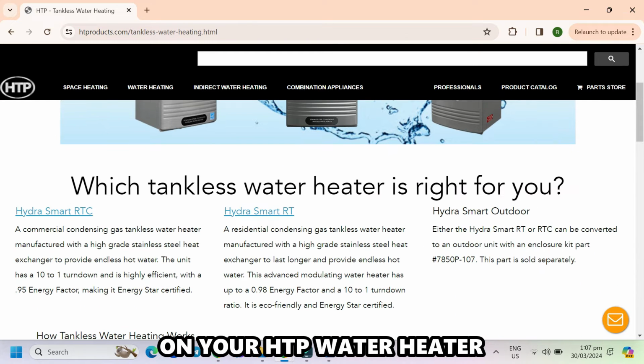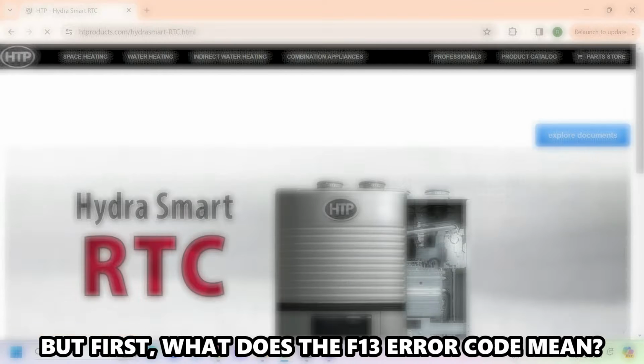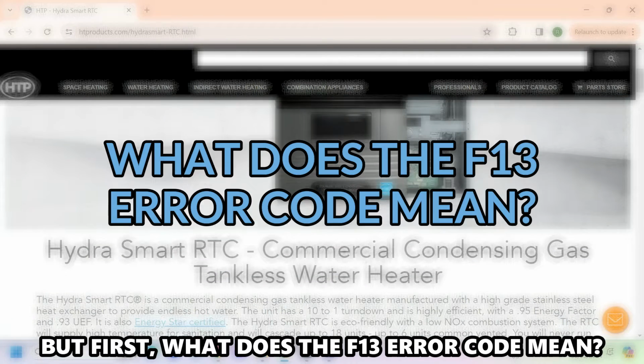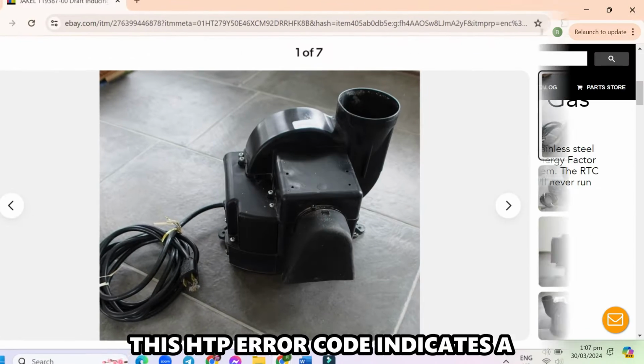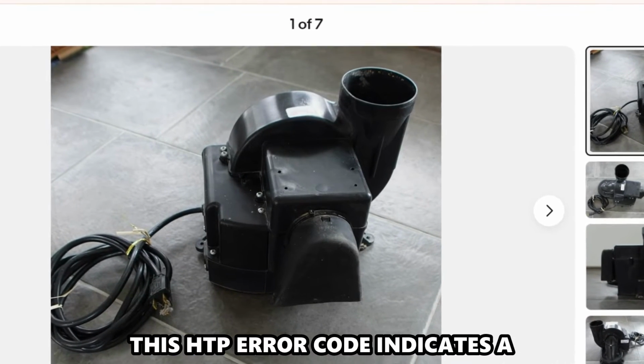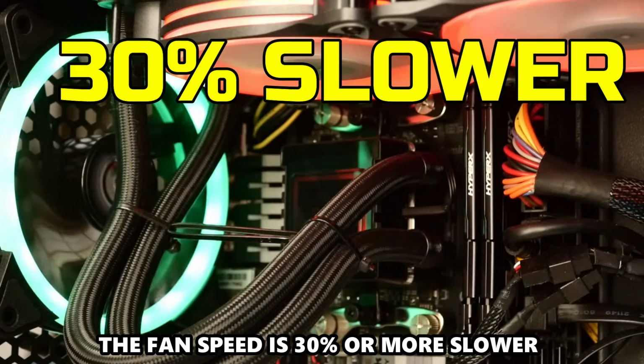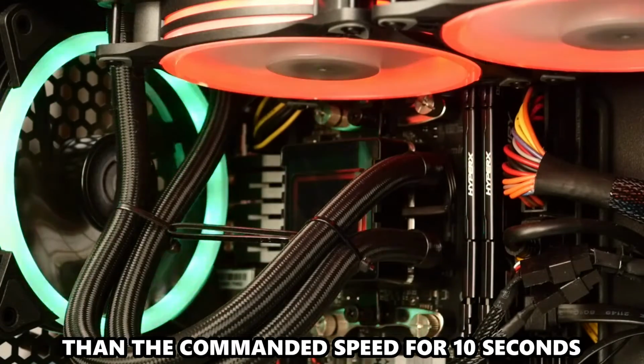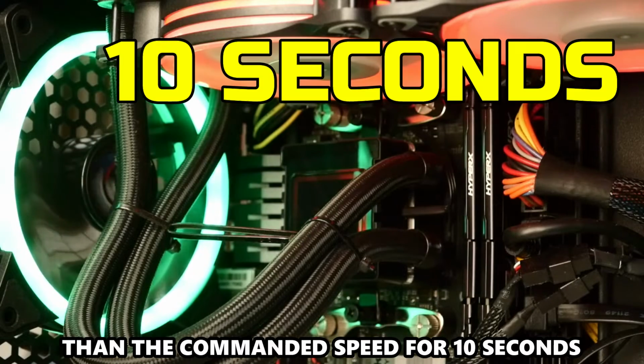But first, what does the F13 error code mean? This HTP error code indicates a problem with the fan speed. The fan speed is 30% or more slower than the commanded speed for 10 seconds.